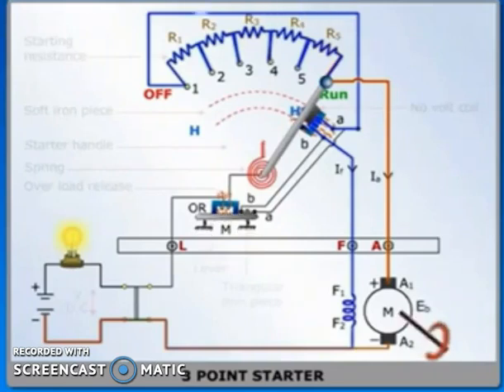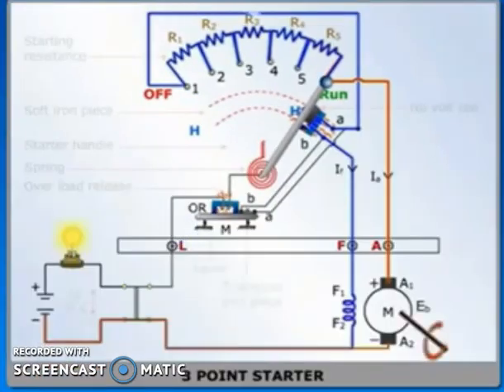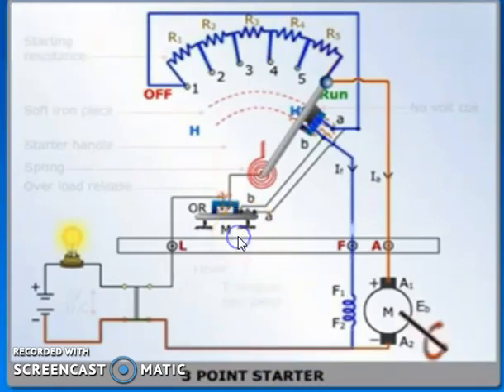Another protection device: overload release coil, OR. This is provided in series with the armature circuit. In case armature current exceeds a preset value due to overload, OR becomes more strong and attracts the movable soft iron arm pivoted at one end.